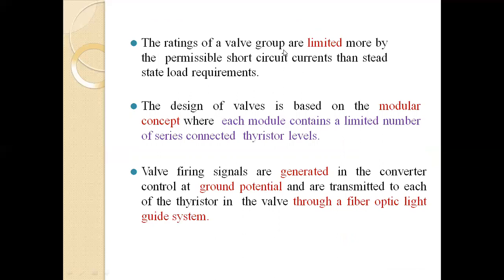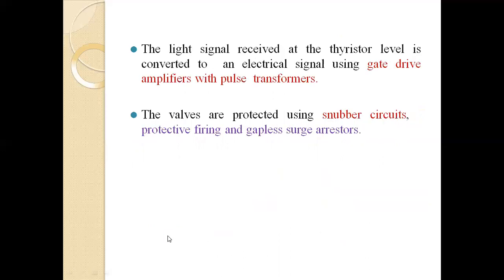Next, the rating of the valve group is limited more by the permissible short circuit current than by steady state load requirement. The design of the valve is based on the modular concept, where each module contains a limited number of series connected thyristor levels. Valve firing signals are generated in the converter control at ground potential and are transmitted to each of the thyristors in the valve through a fiber optic light guide system.